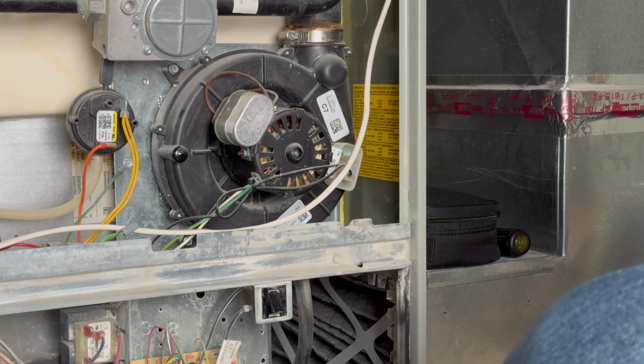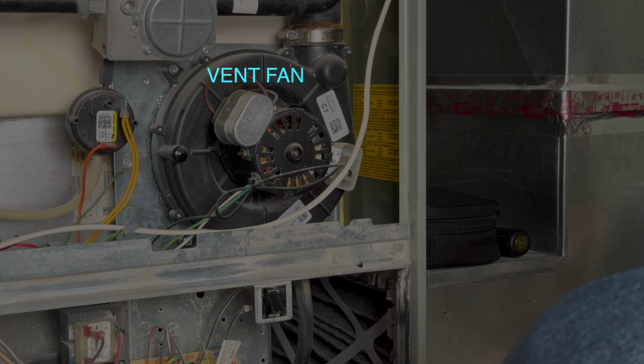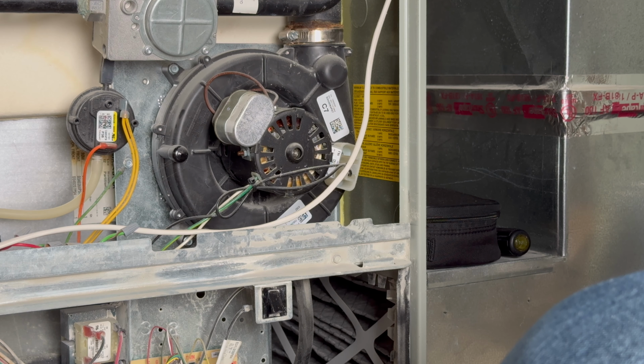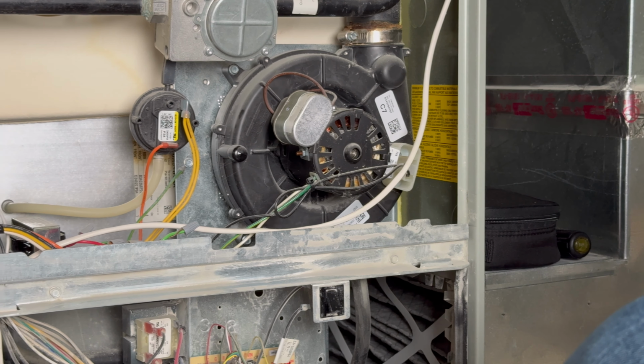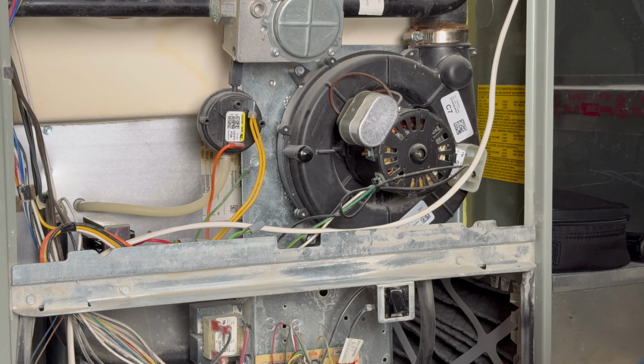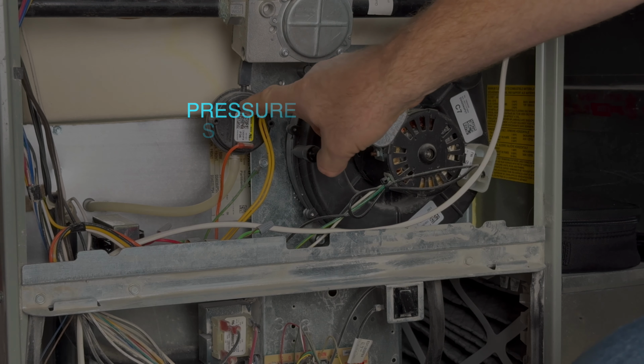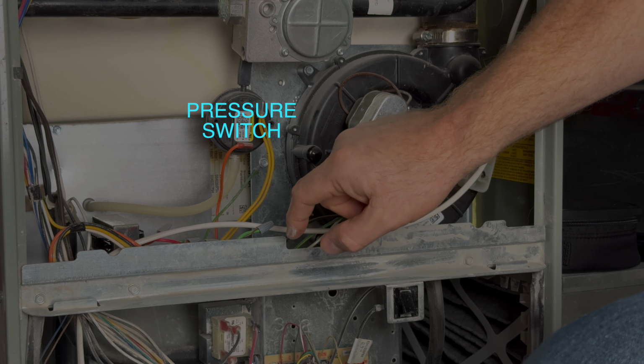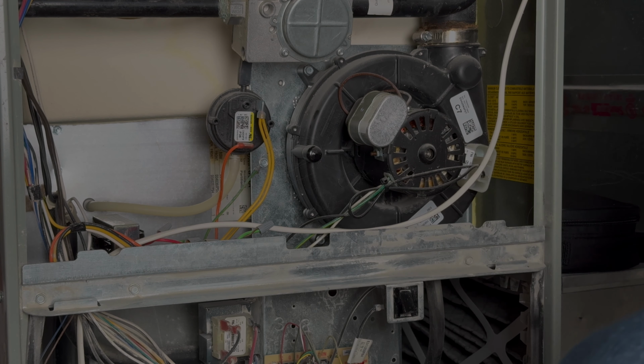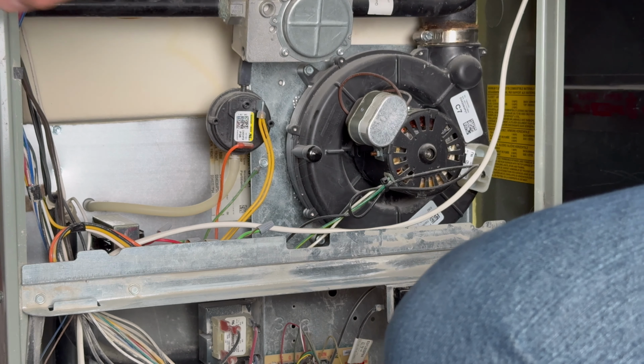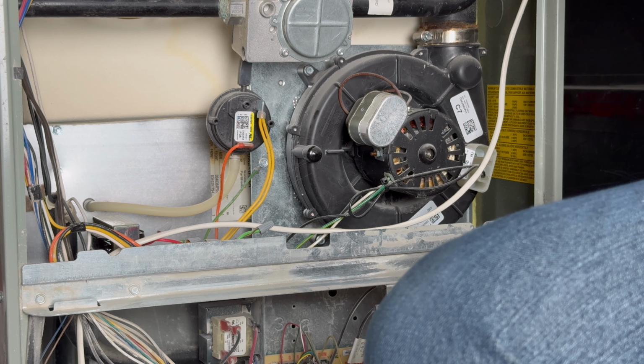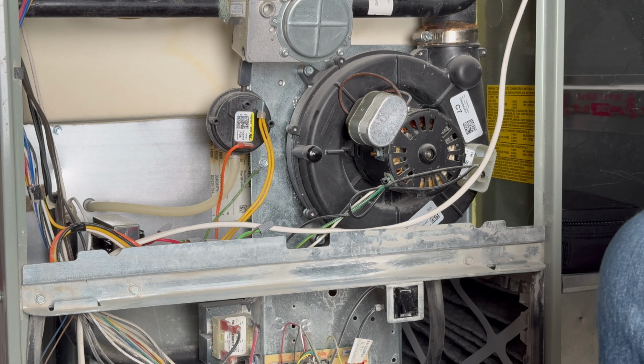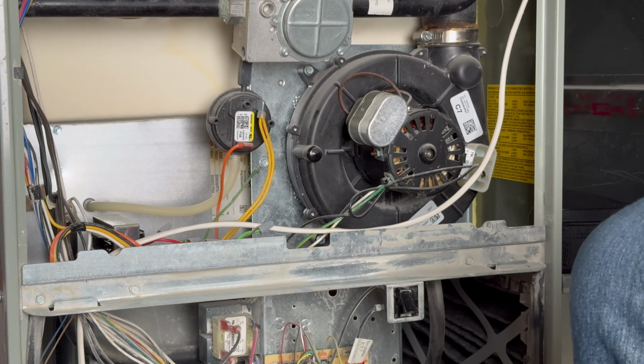What we're looking at here is the exhaust or combustion fan. It's actually called the vent fan on the schematic. This being a gas-fired furnace, the exhaust fan removes the CO while the unit is heating. Over here, we have the pressure switch. The pressure switch makes an electrical switch based on a preset differential pressure between the suction and discharge side of the combustion fan. Think of it as a safety switch that allows operation after it's proven that the exhaust fan is running and flowing adequately.